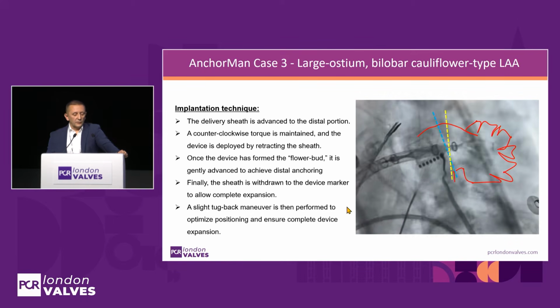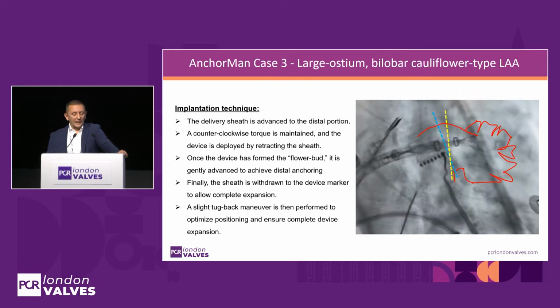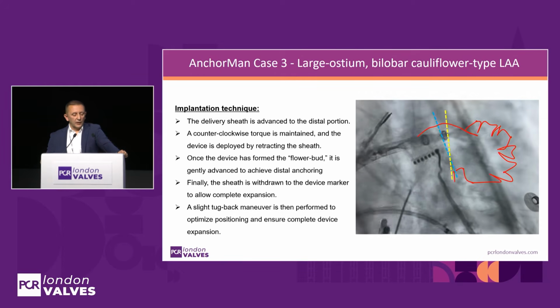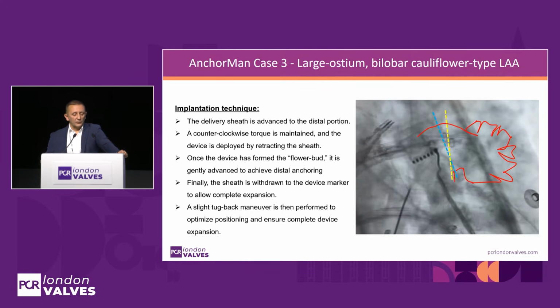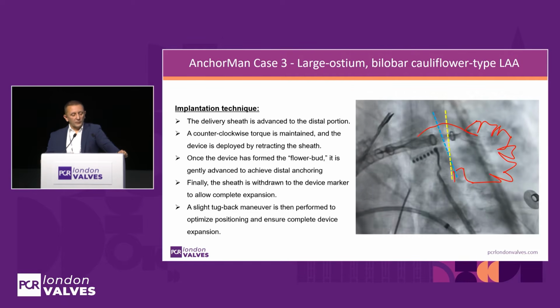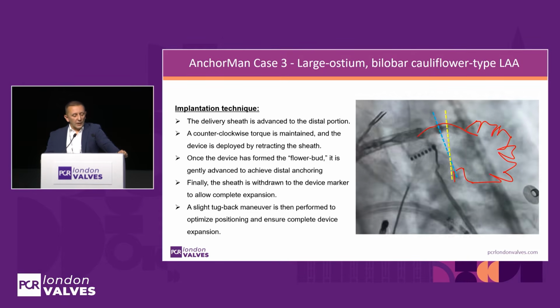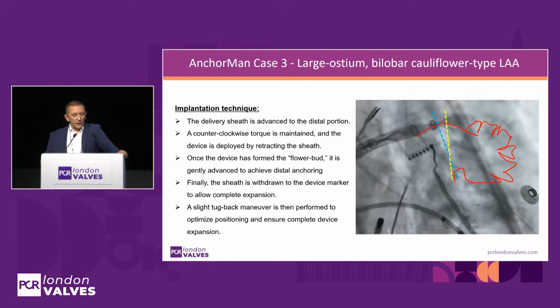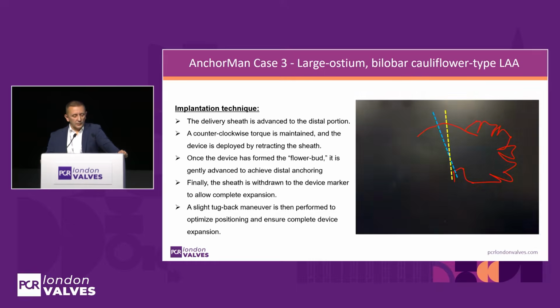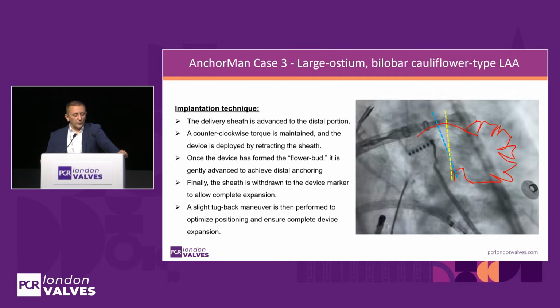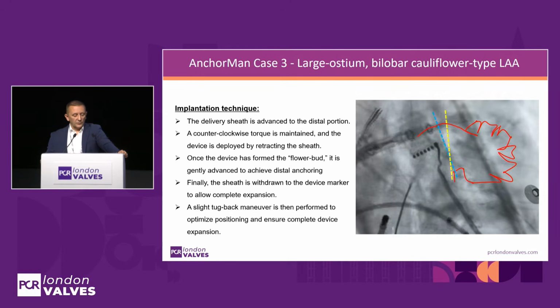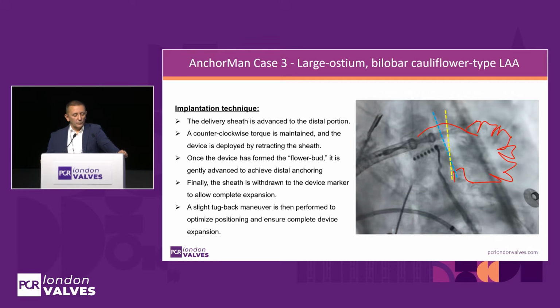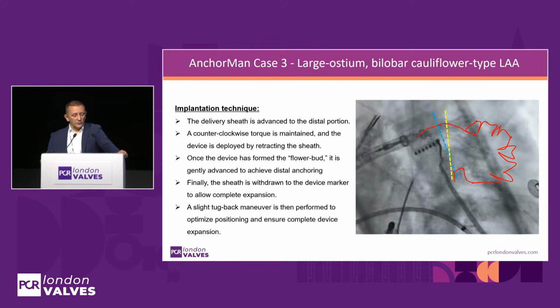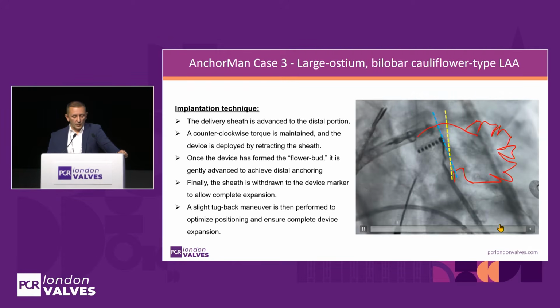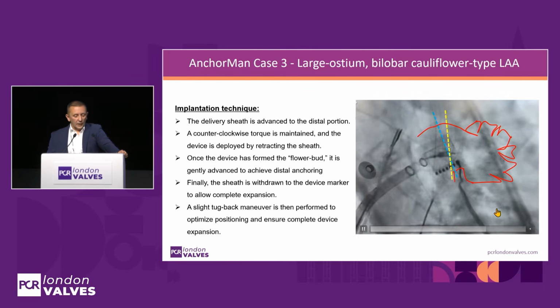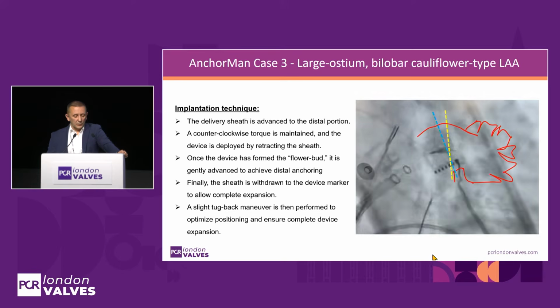So the delivery sheath is advanced to the distal portion, a counterclockwise torque is maintained, and the device is deployed by retracting the sheath. And once the device has formed a flower bud, it is gently advanced to achieve the distal anchoring. Finally, the sheath is withdrawn to device marker to allow complete device expansion, and the slight tug-back maneuver is then performed to optimize positioning and ensure complete device expansion, as you can see here.